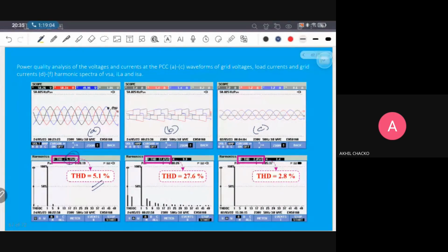And when we analyzed the load current, it is almost a square or pseudo-square wave with one side offset. Here we received 27.6% THD in the load current when power quality was checked. But when we check the grid current harmonics with the effect of our distribution STATCOM operation in our grid connected PV system, we achieved 2.8% THD with the power quality analyzer result.